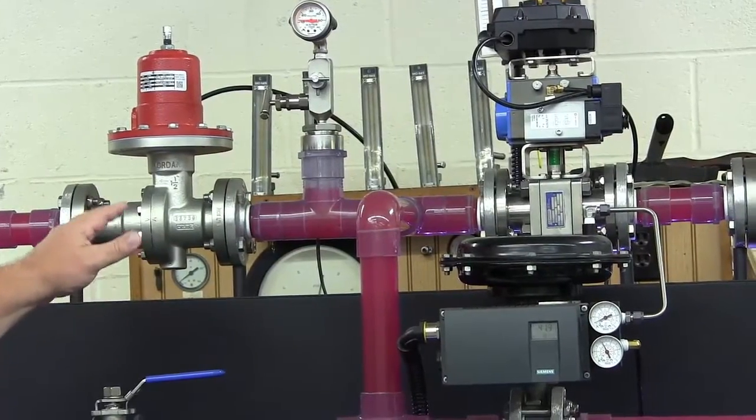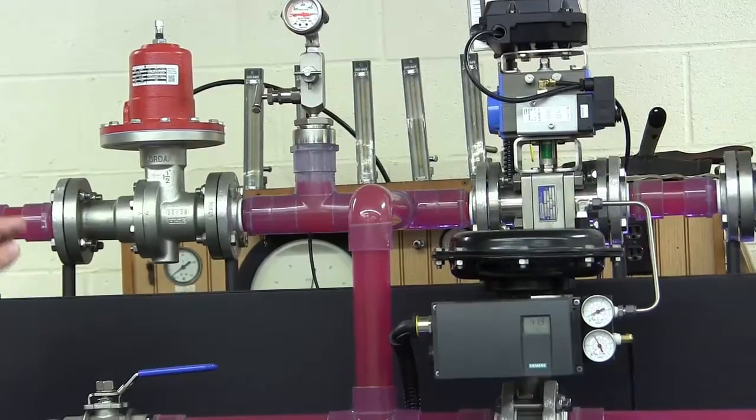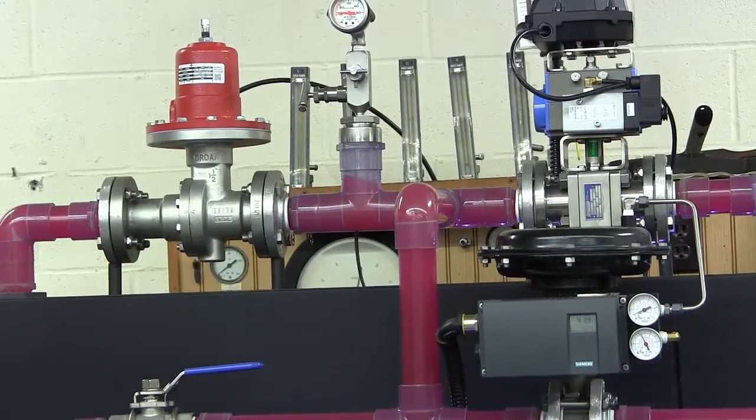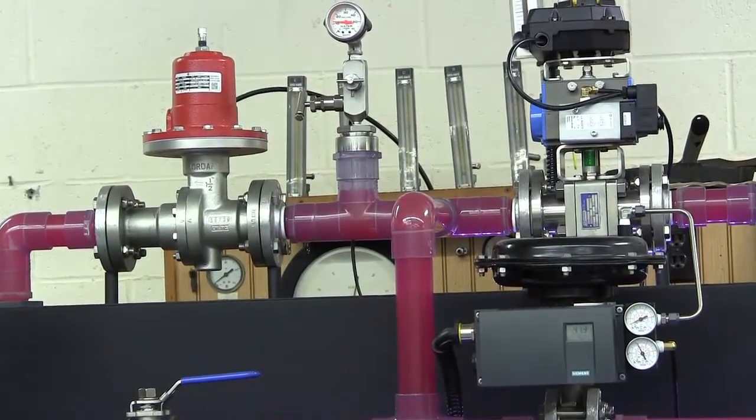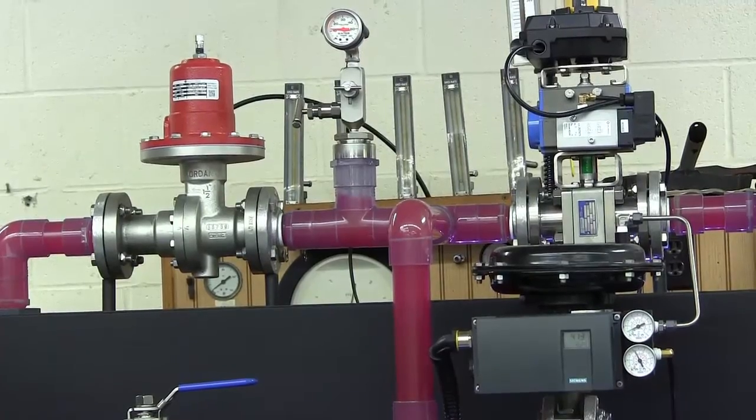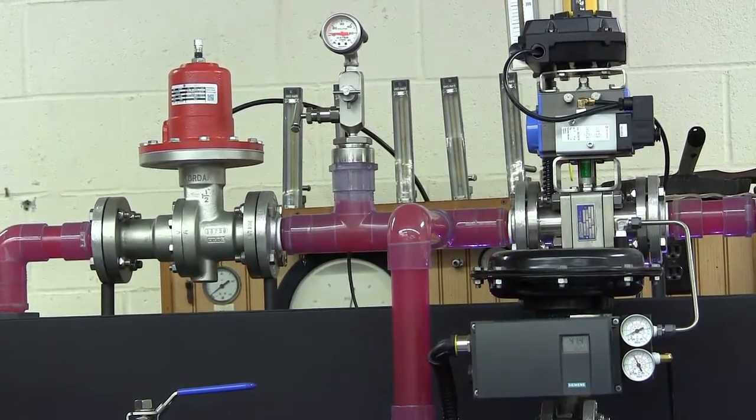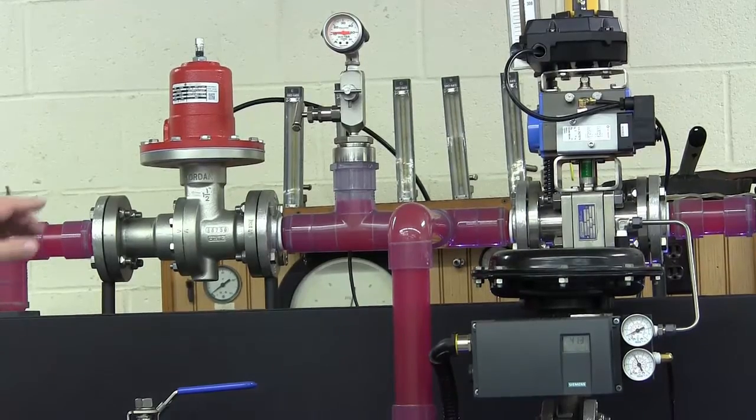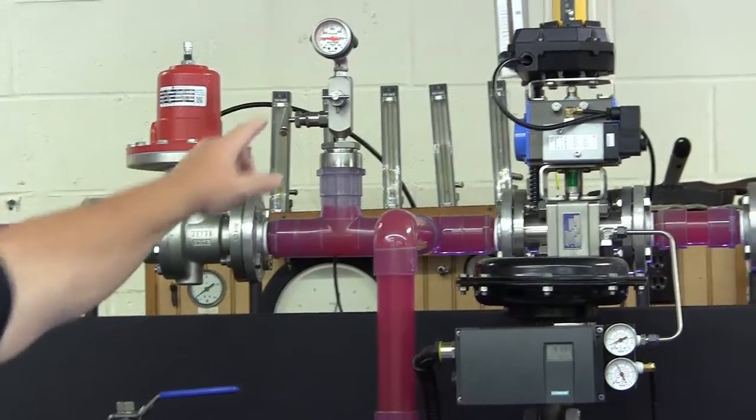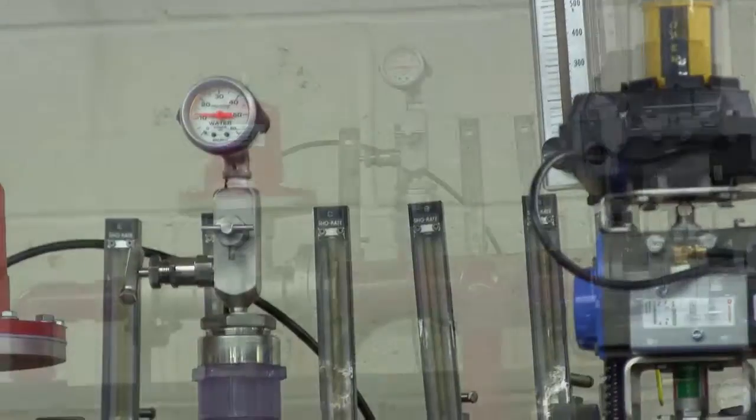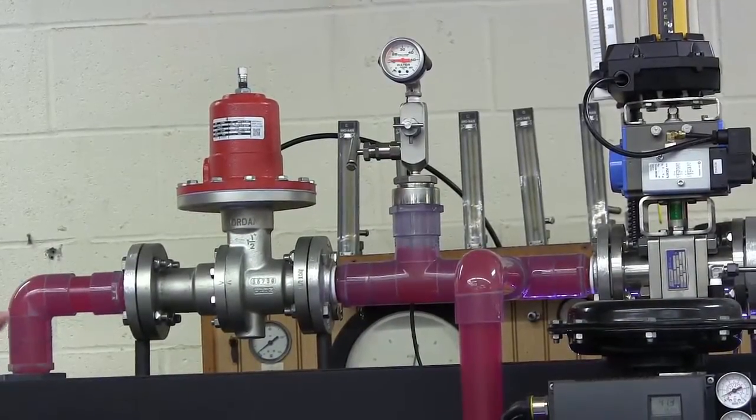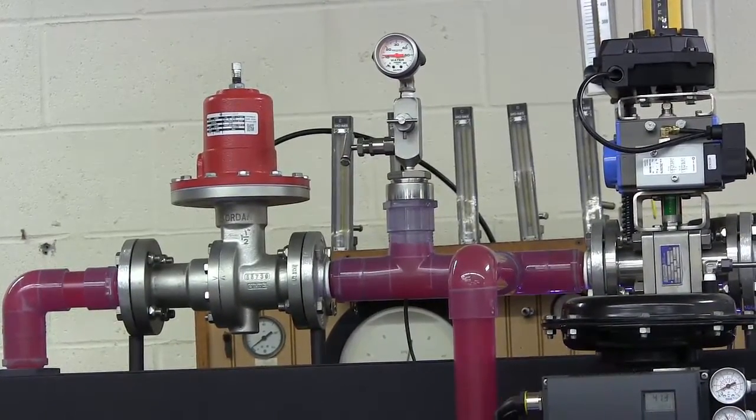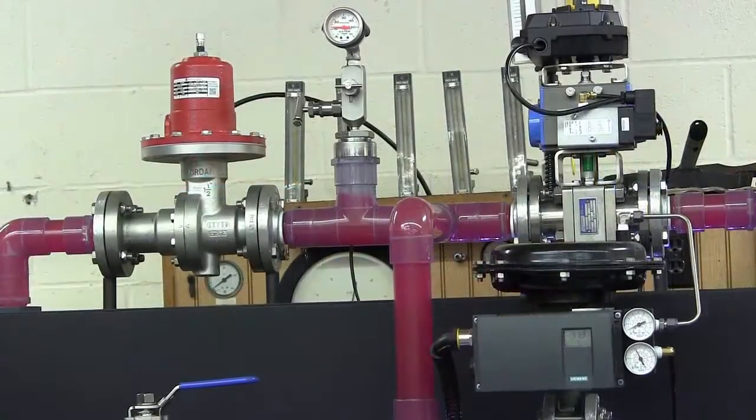Like the mark 75, the mark 50 also employs Jordan sliding gate seat technology. The mark 50 is a self-operated back pressure regulating valve. The range spring holds the seat in the closed position. When the upstream pressure reaches the valve set point, in this case 10 psig, the pressure under the diaphragm will compress the spring, opening the valve and relieving the pressure.